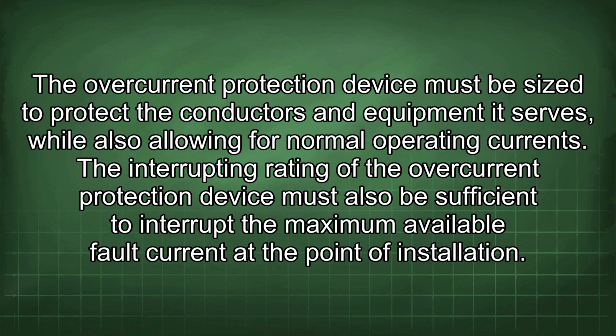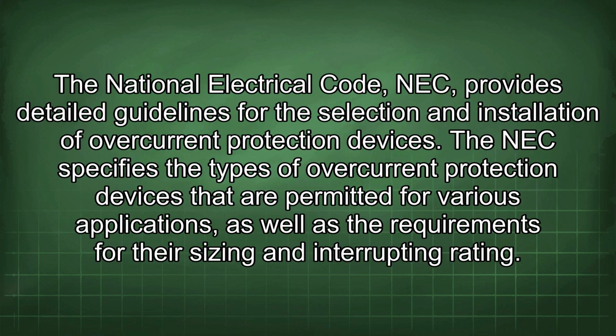The interrupting rating of the overcurrent protection device must also be sufficient to interrupt the maximum available fault current at the point of installation. The National Electrical Code (NEC) provides detailed guidelines for the selection and installation of overcurrent protection devices. The NEC specifies the types of overcurrent protection devices that are permitted for various applications, as well as the requirements for their sizing and interrupting rating.